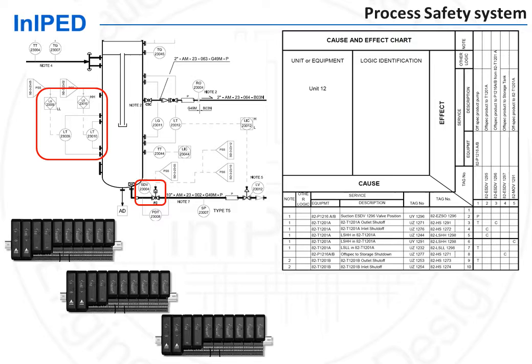As the process safety system performs safety functions, it requires a high level of reliability. The corresponding controllers are either duplicated or triplicated — i.e., instead of one controller there will be three controllers, so that if one fails, the other two will detect the failure and take over and implement the action.